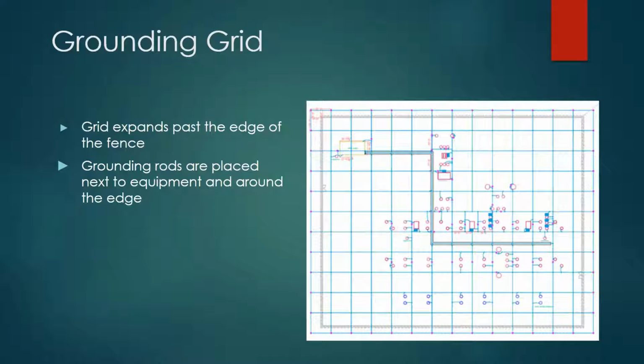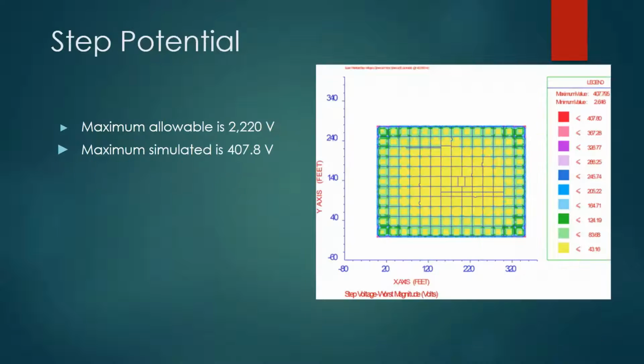So here is our grounding grid, our preliminary design at least. The grid expands past the edge of the fence in every direction. That's to get fault current away from the equipment as quickly as possible. The purple dots are grounding rods, which are 20-foot rods pounded vertically into the ground. Their purpose is to get fault current as deep into the earth as quickly as possible. The reason behind that is the deeper you go into the earth, the less resistive the soil gets as it's moist. So that will help us to dissipate fault currents faster.